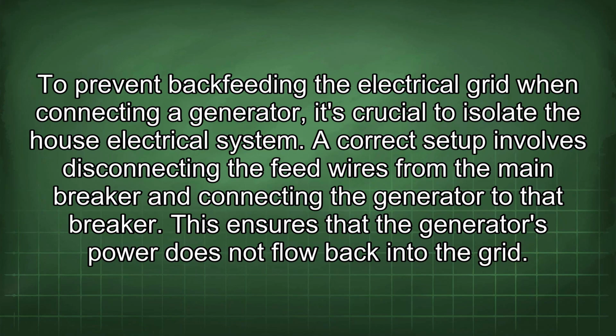To prevent backfeeding the electrical grid when connecting a generator, it's crucial to isolate the house electrical system. A correct setup involves disconnecting the feed wires from the main breaker and connecting the generator to that breaker. This ensures that the generator's power does not flow back into the grid.